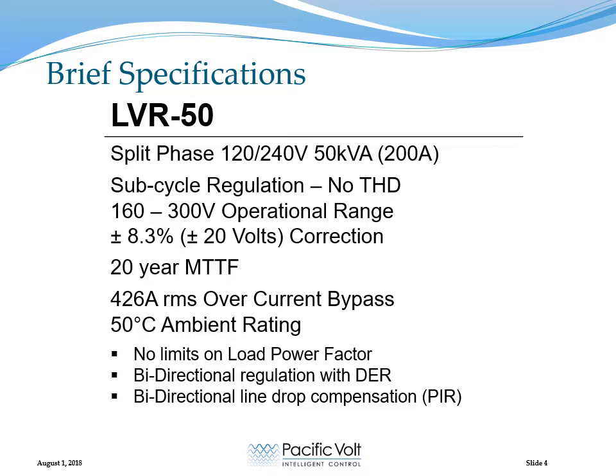At 426 amps, it will go into an overcurrent bypass, which automatically resets when the current drops to more normal. It has no limits on the load power factor, meaning it will regulate a totally capacitive load or a totally inductive load. It has bi-directional regulation to support distributed energy resources. It also has programmable bidirectional line drop compensation.